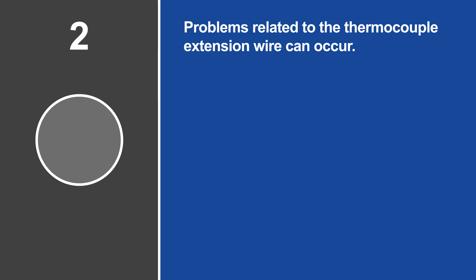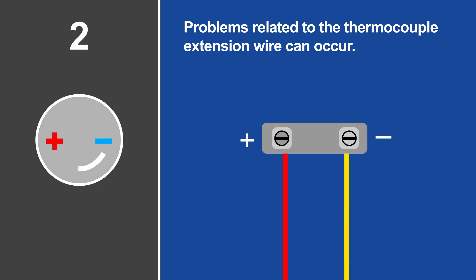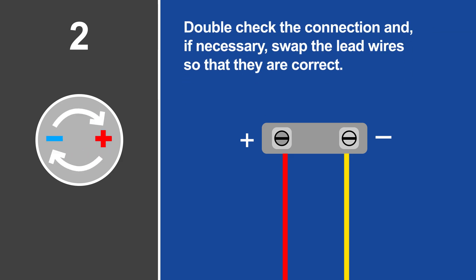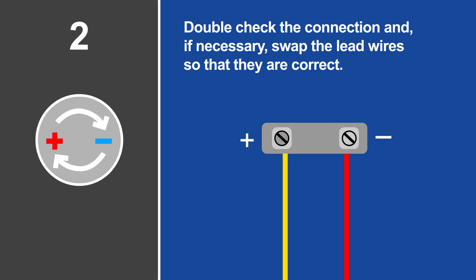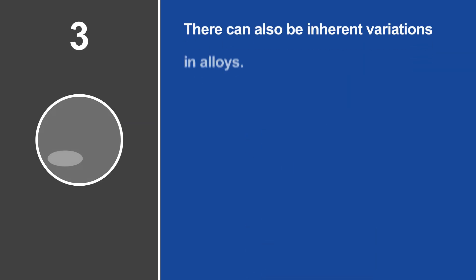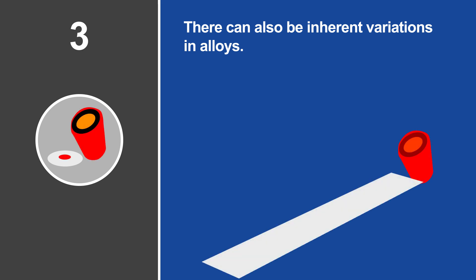Problems related to the thermocouple extension wire can occur. If the polarity of the thermocouple lead wires is reversed, the measured temperature will also be incorrect. The solution is to double-check the connection, and if necessary, swap the thermocouple lead wires so that they are correct. There can also be inherent variations in alloys.